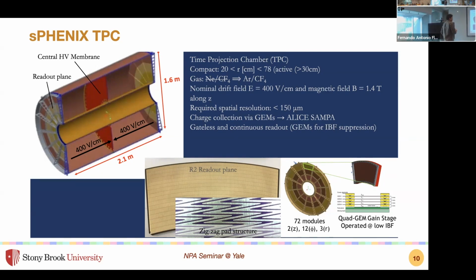But another noticeable thing is the readout plane was not Cartesian, it was a polar coordinate system. That helps you reduce the dead area as much as possible, because you want to have as many samples as possible without losing too much information. So we had a very tight constraint on the acceptance, the physical acceptance of the readout.